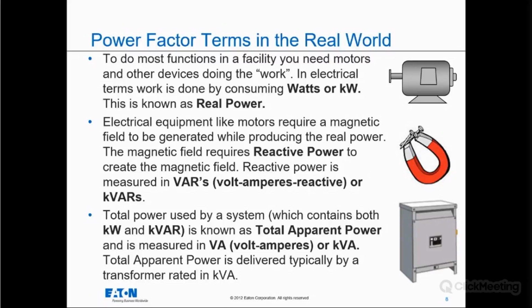If you stop and think about it, if you walked up and pushed the start button on a full voltage non-reversing motor, what's the first thing that has to happen for the shaft to turn? You have to generate the magnetic field to turn the shaft. So this is that reactive power. Some people even refer to it as magnetizing power. It is measured in volt-amperes reactive, or kVAR. And then finally, total power used by the system contains both kW and kVAR and is known as total apparent power. It is measured in volt-amperes, or kVA. Total apparent power is typically delivered through a transformer. That's why a lot of people recognize the kVA terminology, because typically the transformer out front of the plant is rated in kVA.